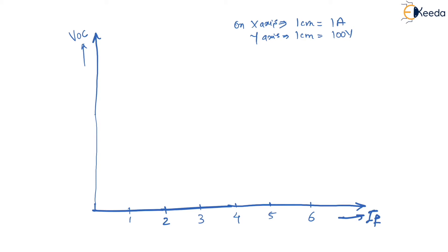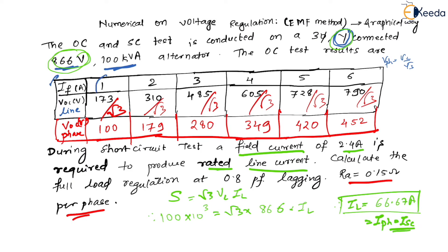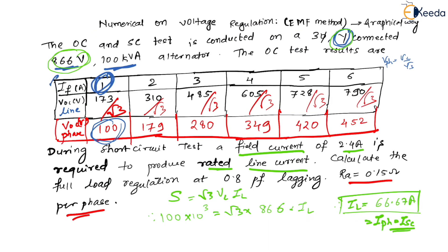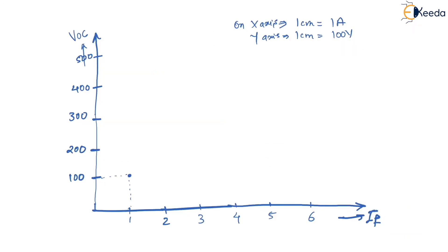On the x-axis, each 1 cm distance indicates 1 A of field current, giving points at 1, 2, 3, 4, 5, 6. On the y-axis, marks are at 100, 200, 300, 400, 500 V. When field current is 1 A, VOC phase = 100 V — this is the first point. When field current is 2 A, VOC = 179 V — the second point, just below 200 V.